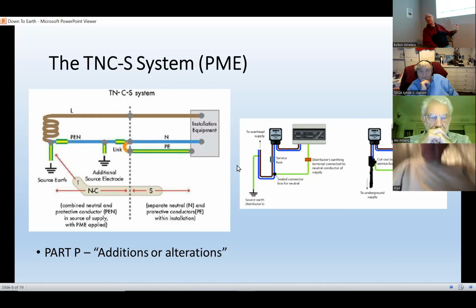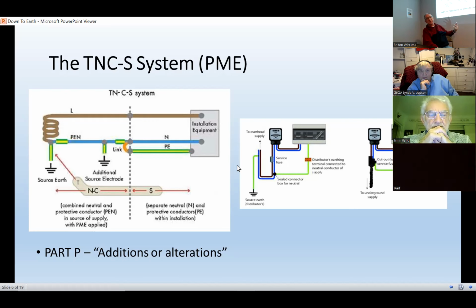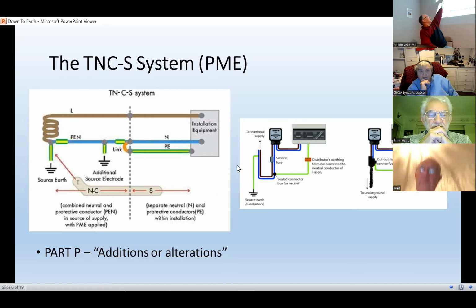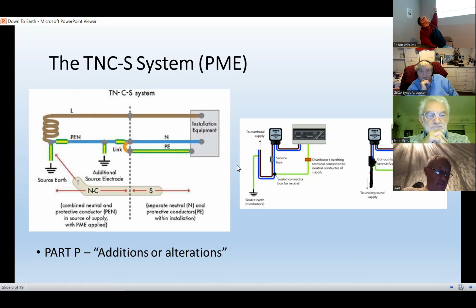The reason they do this, and it's more and more common in new build properties, is because it's cheaper and easier to put in. It saves them money. But what you have along the run of that neutral between your house and going back to the substations and so on, is multiple earth connections on the neutral line. Hence its other name, PME, protective multiple earthing.